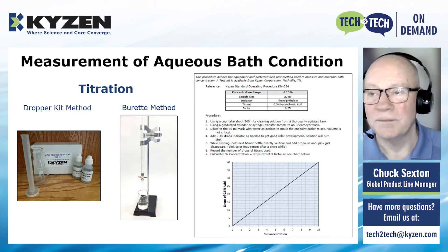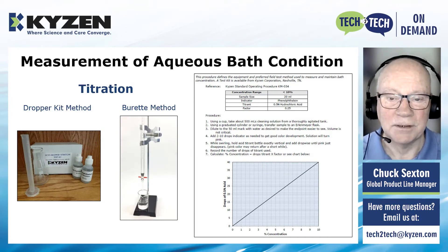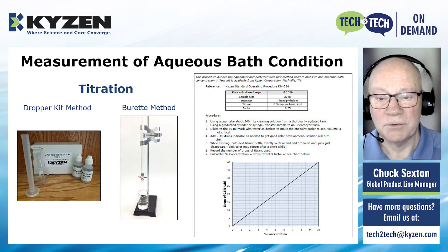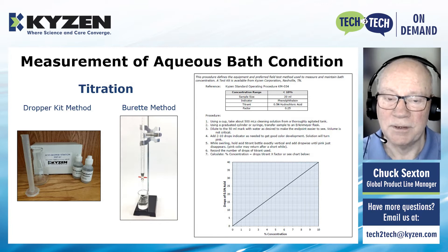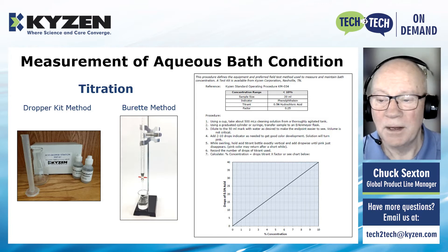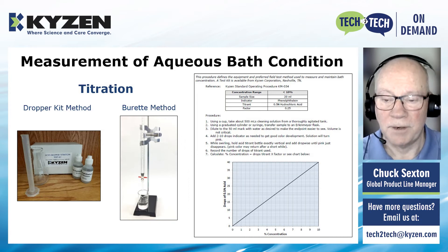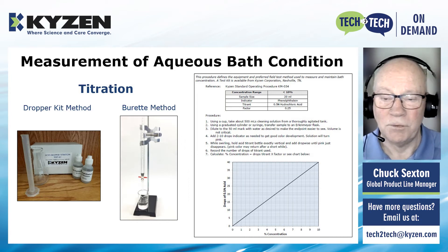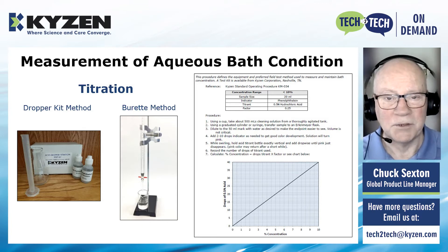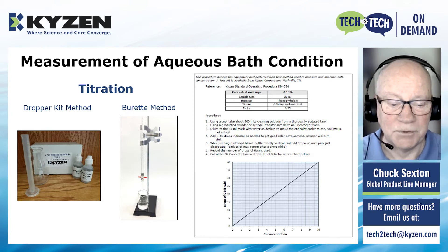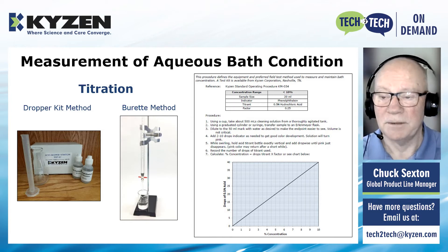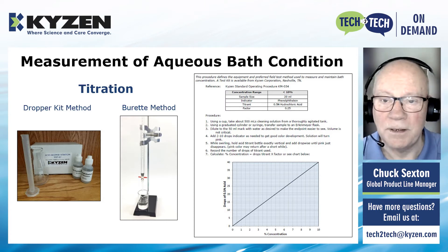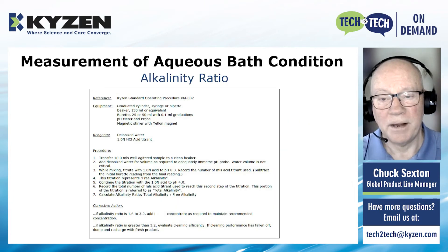The tried and true conventional method is titration. Generally, we'll help a customer for two months or so — we'll measure the concentration by titration and then try one of these simpler methods. The titration methods involve either a dropper kit, which can be used on the plant floor, or a burette method, which is usually found in a laboratory. We relate the drops or the milliliters of titrant to the concentration of the cleaning chemistry. Very accurate method.